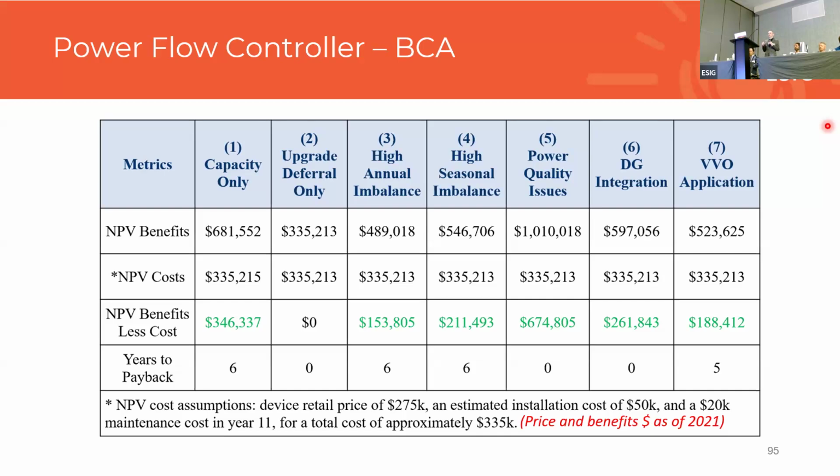And another important aspect to this device, which some people question, is how long does it take to deploy? Usually it's about a day to do the commissioning and dropping it on site. As long as the pad is already there, they can drop it and commission it pretty quickly. It's pulling some lines down from the line, the riser goes underground, and then terminating them on the device, and it tends to go pretty quick.